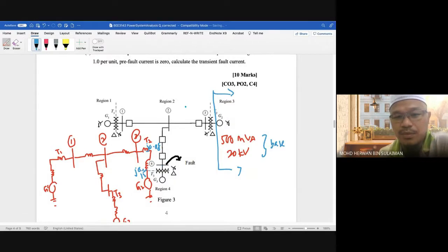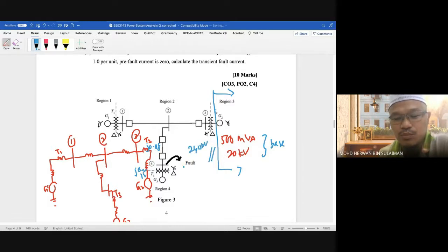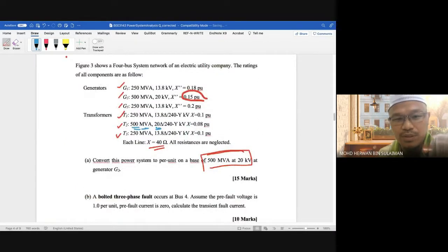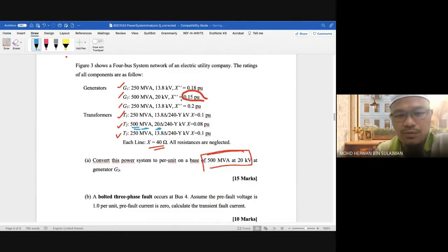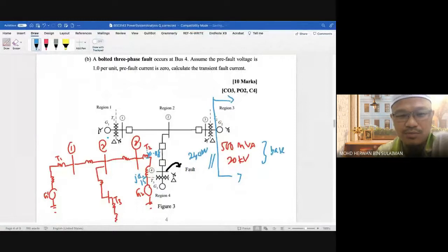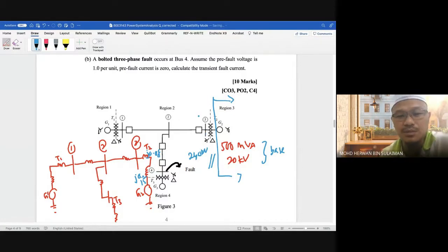Since the base is 500 MVA and the transformer rating is the same, the voltage base on the 20kV side is fine. The transformer steps up from 20kV to 240kV, so the voltage base at the transmission line side becomes 240kV. Now we need to work outward from the reference in all directions.